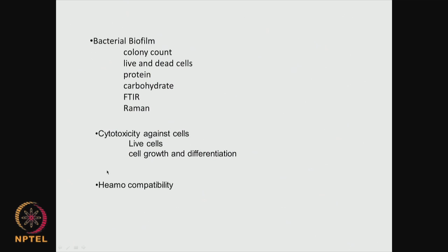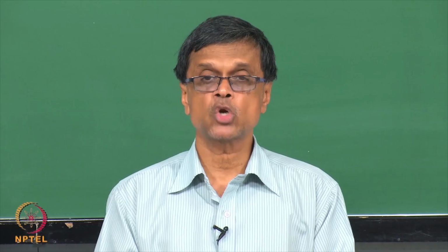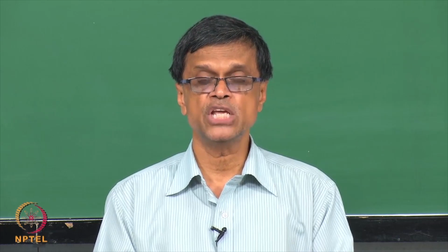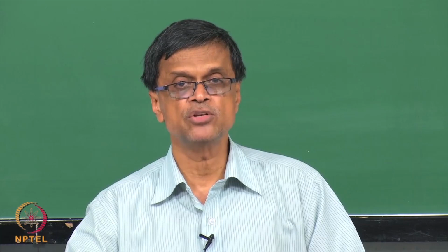Then I need to know the hemocompatibility. That means if it is a blood contacting device, is the material going to be very toxic to the blood? Will it create responses so that the blood starts clotting on the surface, which is very, very dangerous. Okay. So you see a lot of biological studies I need to look at. I need to look at bacterial biofilm related.